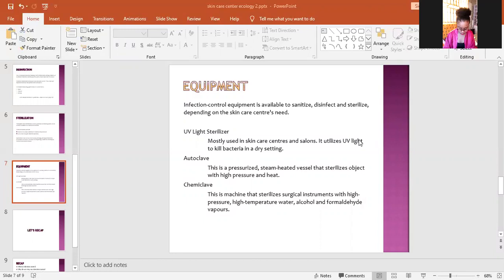For high frequency and galvanic, the electrodes are glass. So you can imagine putting a glass electrode into very hot equipment. What will happen? It will burst. It will break. Do you understand? It will get shattered. So you are not advised to put your glass electrodes into an autoclave. Don't sterilize them. Just sanitize and disinfect them, dry them, then put them in a small UV sterilizing unit. So do not put them in your autoclave.